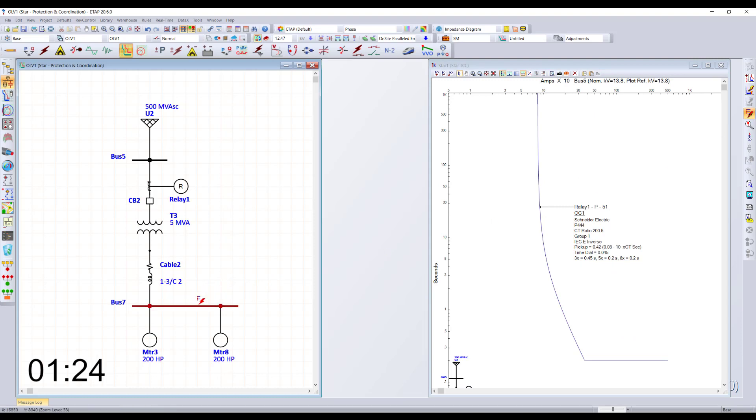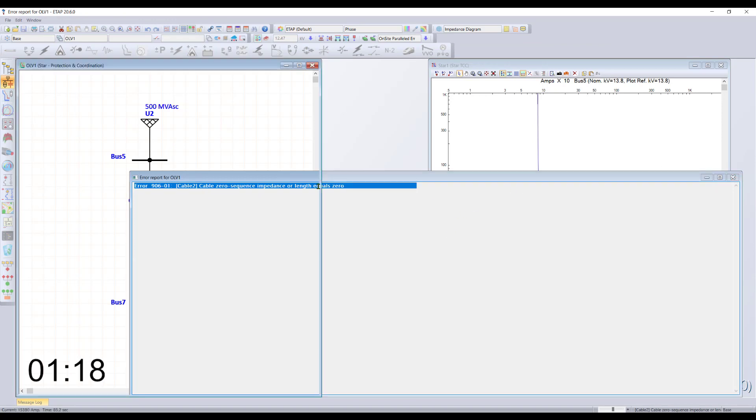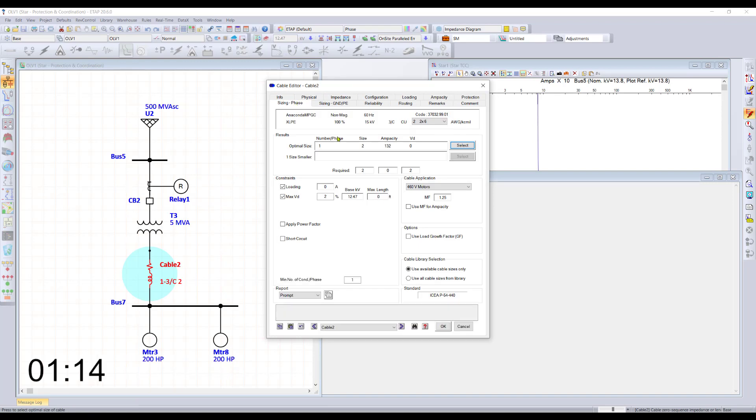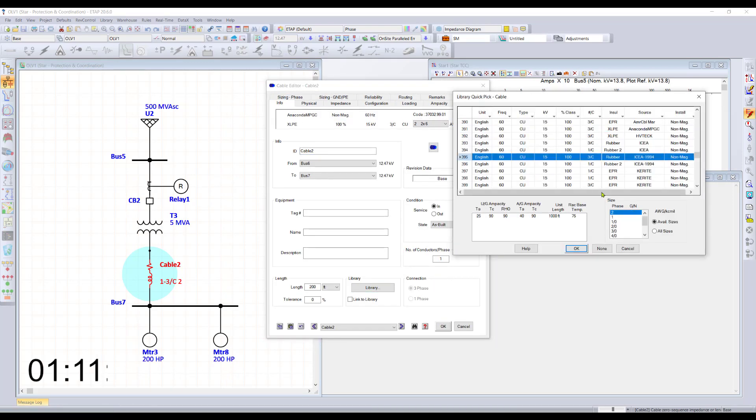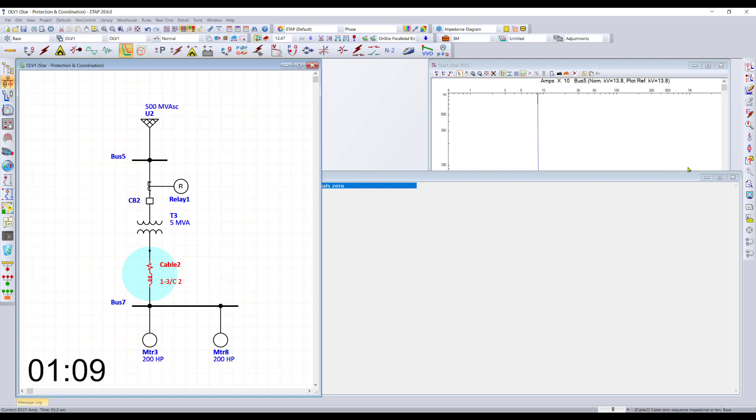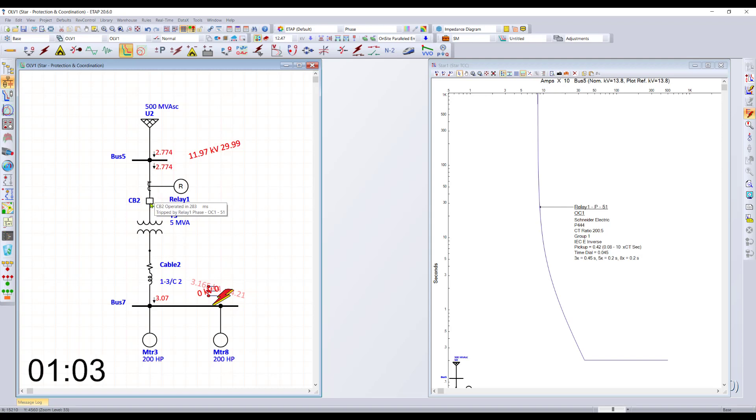Ready to test this protection? No problem. Just simply drag and drop the short circuit arrow. Once again, the program is letting me know that I picked a cable that is missing some information. We'll go ahead and pick a different conductor and rerun our test again. We can see that this relay picks up and trips the breaker in 283 milliseconds.